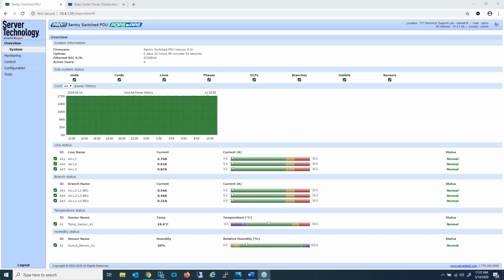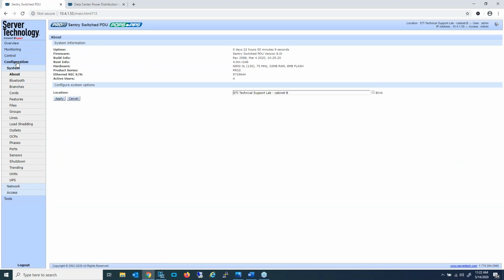Okay, well, the PDU itself doesn't have a policy to force a password change on a period, so you'd be managing that externally, and you're clearly talking about changing on more than just one PDU. What we looked at today was just one PDU. Amongst the simplest ways for mass configuration, much easier than logging into every single PDU, the easiest way is to use our STIC protocol, what's known as the Server Technology INI protocol, which we did discuss in last week's session.